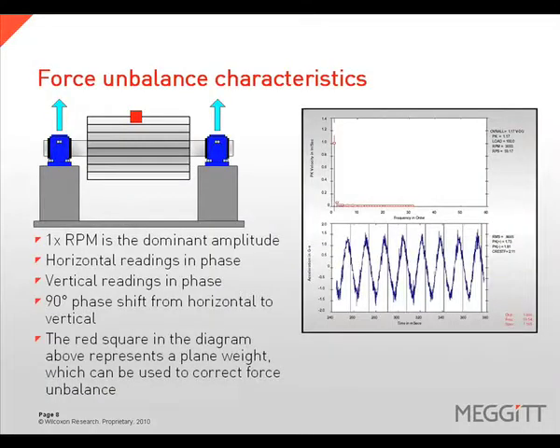Force unbalance will exhibit a dominant 1 times rotational speed amplitude. The horizontal as well as the vertical phase readings will be in phase, with a 90 degree phase shift from the horizontal measurement plane to the vertical measurement plane. This type of unbalance can be corrected with a single plane weight placement.